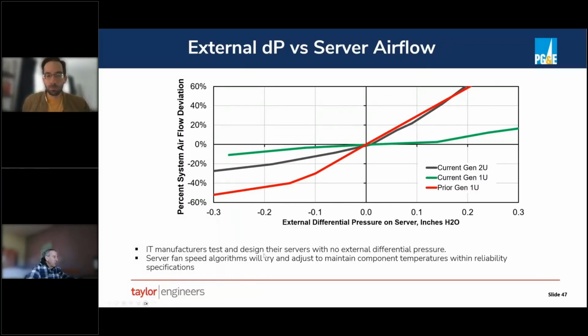Generally, servers are tested and designed with no external pressure, so they're not expecting to have any. You give them extra pressure, they'll work fine. You give them negative pressure, they start to have trouble. The fan speed algorithm will try to adjust to maintain temperatures within reliability specification. So the fan will speed up if it's getting less air, but at some point we'll run out of fan.